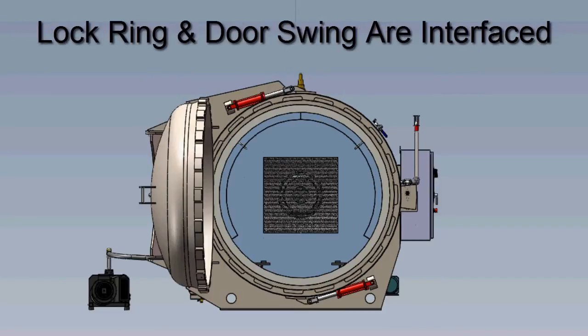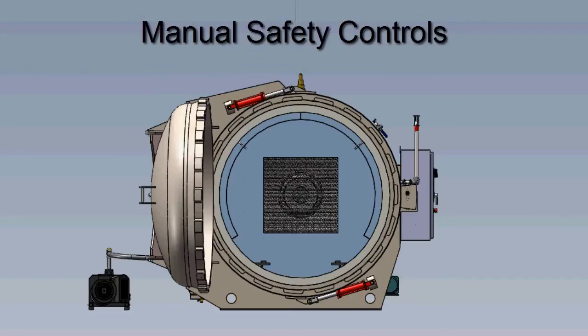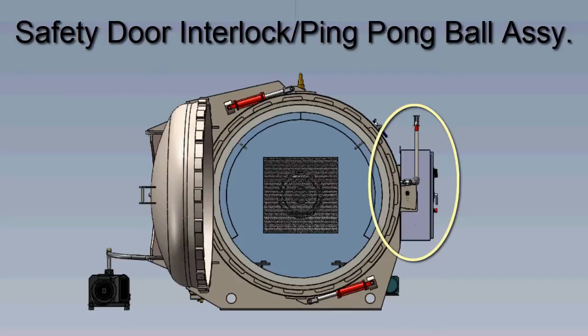The lock ring and door swing operation are interfaced to prevent operation when pressure of 1.5 PSI is present in the autoclave. The safety door handle interlock and ping pong ball assembly are some of the manual and visual safeties included in these systems.